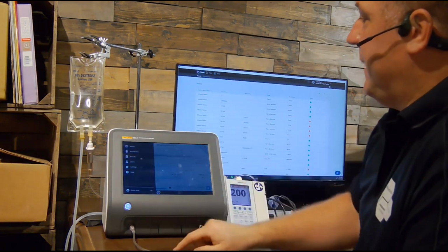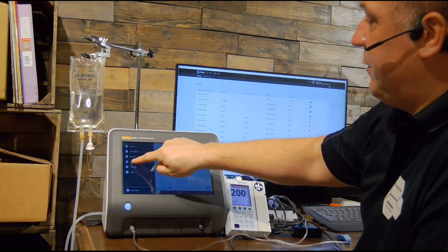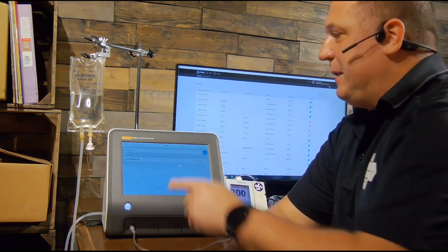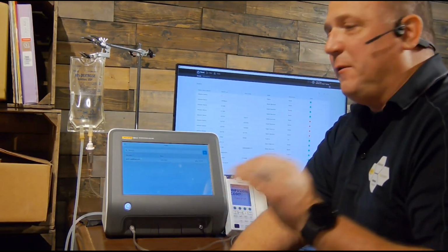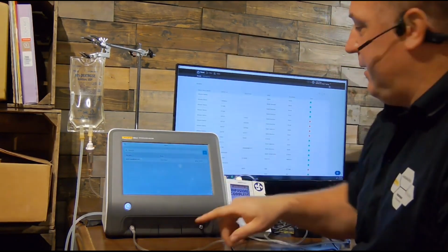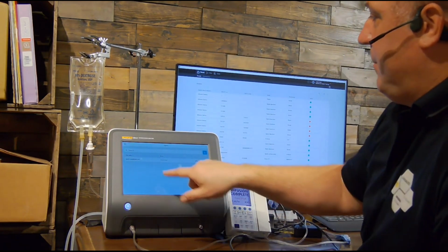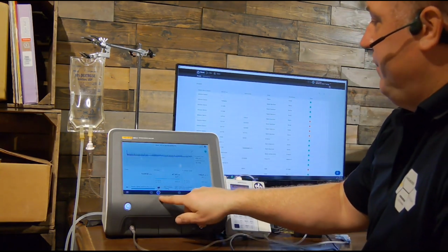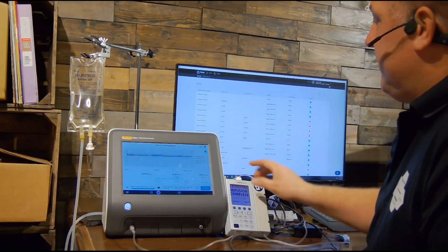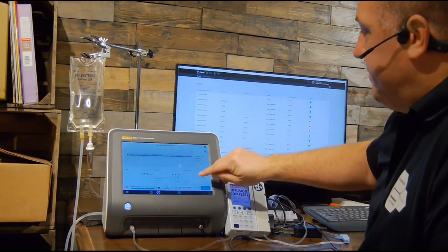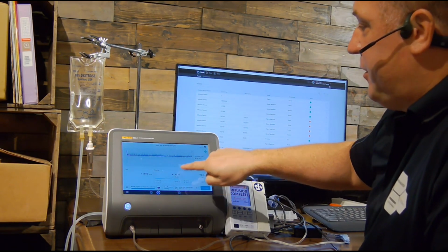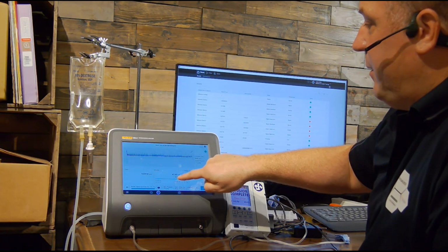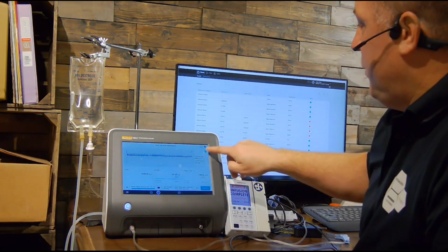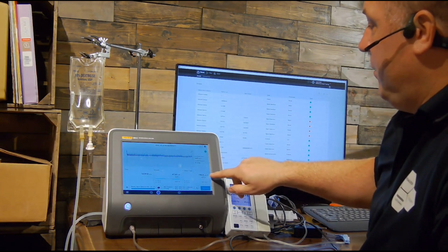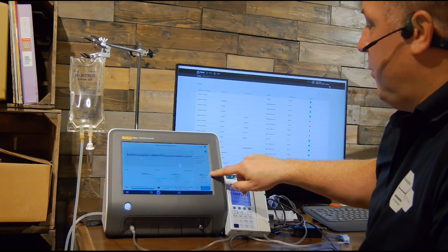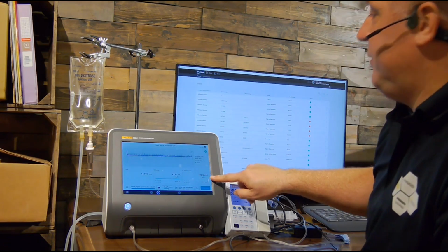Back out. Let's go back in here one more time. So assets, procedures, results, users. If I have OneQA Lite, I'm allowed to have 1 user. If I have the full-blown OneQA, I can have everybody. Oh, my test stopped. So I'm going to pause on users. Let's go back to 1, and I'm going to hit silence on this. And you'll notice now our total volume was 47.62 milliliters. We had 50 set, so that's a negative 4.8% tolerance, which is passing. And my mean flow was 190.5 milliliters an hour. We had 200 set, or 4.7% tolerance, and it passed.